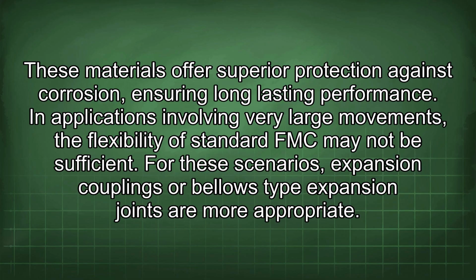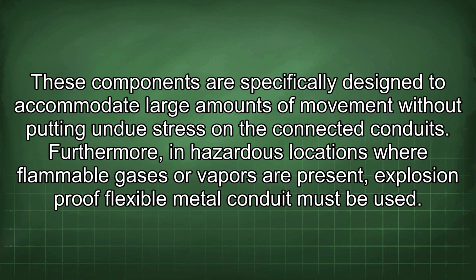In applications involving very large movements, the flexibility of standard FMC may not be sufficient. For these scenarios, expansion couplings or bellows-type expansion joints are more appropriate. These components are specifically designed to accommodate large amounts of movement without putting undue stress on the connected conduits.